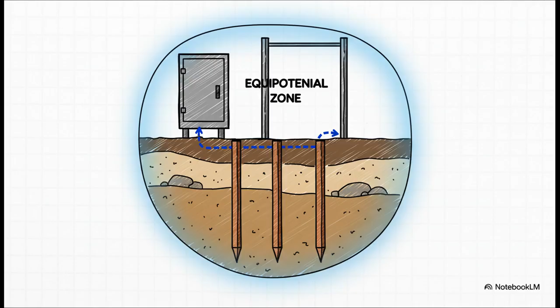Layer 1, the foundation of everything, is a really solid earthing system. This means driving big metal rods deep into the ground to get a great connection to the earth. It also means bonding, connecting all the metal parts together. The idea is to create an equipotential zone. If a fault happens, everything rises to the same voltage at the same time, so there's no dangerous difference from one spot to another.